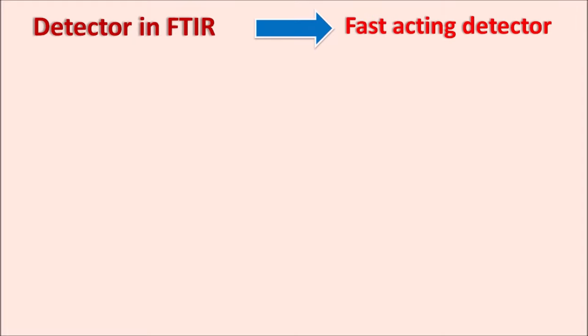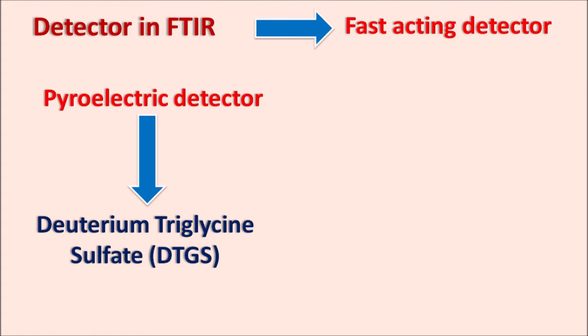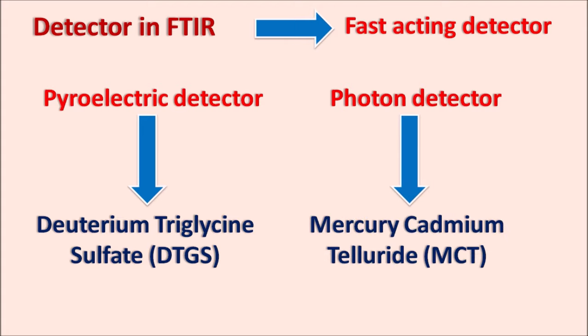For the detector in FTIR: since FTIR is highly accurate, precise, and fast, a fast-acting detector with low response time must be selected. Commonly used are pyroelectric detectors made of deuterium triglycine sulfate (DTGS), or photon detectors using a semiconductor filled with mercury cadmium telluride (MCT). Both detectors have a fast response and are therefore suitable for use in FTIR.